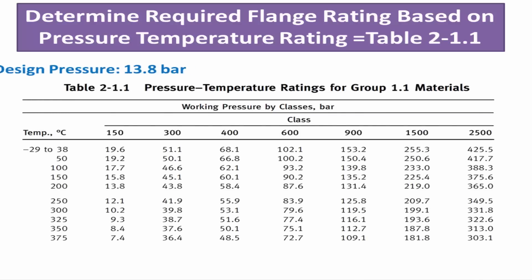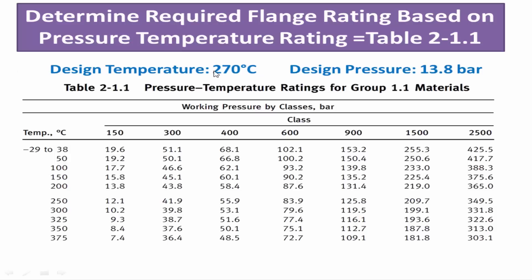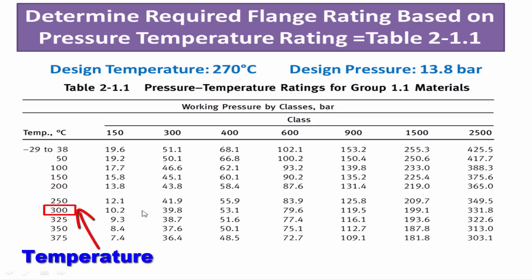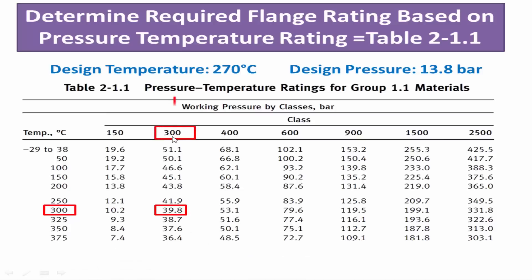In Table 2-1.1, select the flange rating class based on the given existing piping system temperature and pressure. Consider the nearest temperature and pressure values in the table. For example, given a temperature of 270 degrees Celsius, consider the nearest value in the table, which is 300 degrees Celsius. Similarly, consider the pressure value. So finally, for the existing piping system, the appropriate flange class is 300.